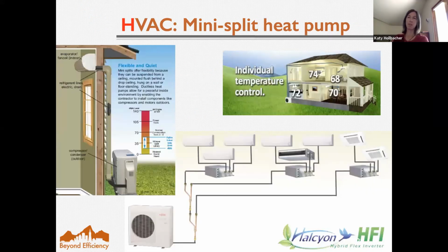So what is a mini split heat pump? We haven't even really talked about heat pump technology yet. A heat pump is actually extracting heat from ambient air rather than just directly creating heat through electric resistance. So the warmer the temperature of that ambient air, the more heat there is in the air to extract and pump into air that you're going to put inside, or pump into water, whether it's for space heating or water heating. But this is really the concept.